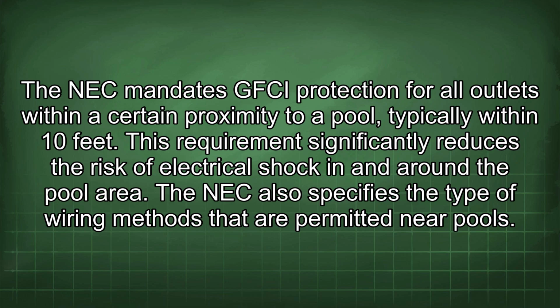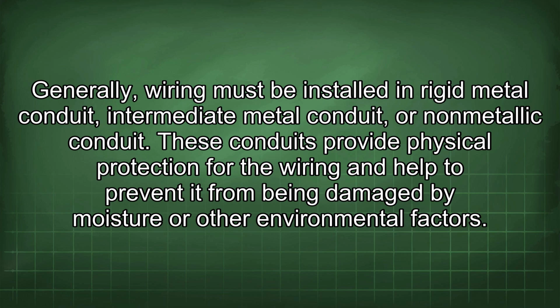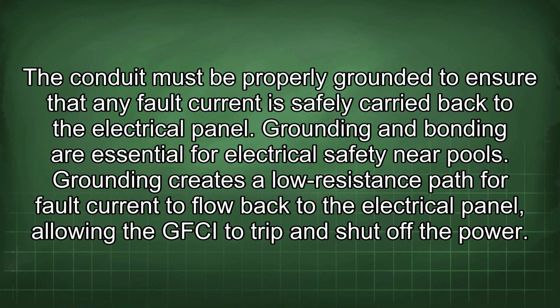The NEC also specifies the type of wiring methods that are permitted near pools. Generally, wiring must be installed in rigid metal conduit, intermediate metal conduit, or non-metallic conduit. These conduits provide physical protection for the wiring and help to prevent it from being damaged by moisture or other environmental factors. The conduit must be properly grounded to ensure that any fault current is safely carried back to the electrical panel.